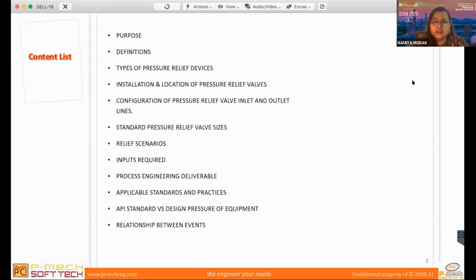Then there is a term called blowdown. All the PSVs you set at a pressure which is your design pressure. When this PSV opens, it starts opening at your set pressure. Once the system is relieved and it closes back to its original position, it does not close exactly at the pressure where you have set the PSV. There is always a difference between the opening pressure and the closing pressure of the PSV, which we call blowdown. Then set pressure, as I already said, is the design pressure.